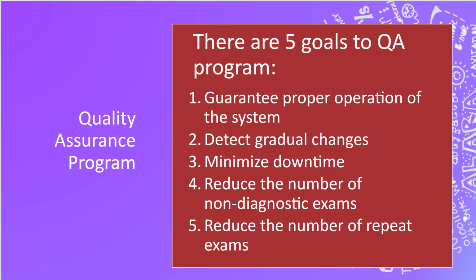We also want to use the quality assurance program to detect gradual changes. So we always are going to check the machine under certain guidelines. We're going to use the same transducer. We're going to use the same output power. We're going to use the same phantoms. We're going to use the same everything. We just want to try to control the environment that we are testing the machine under.